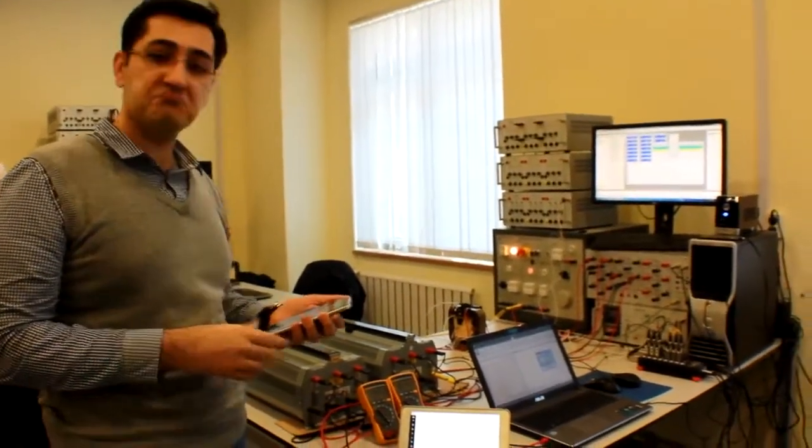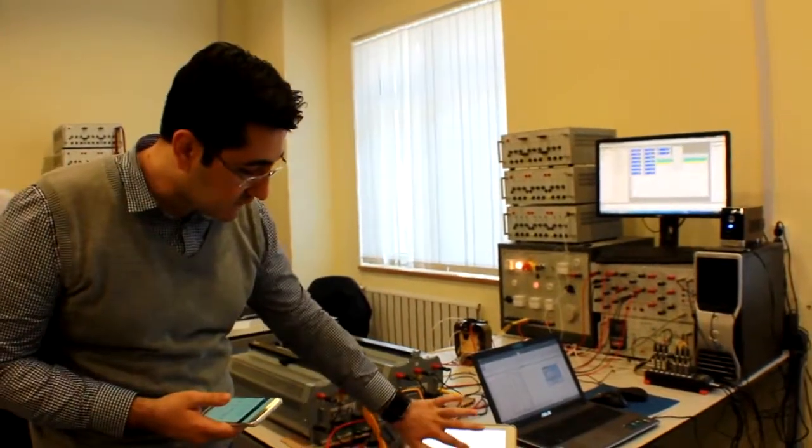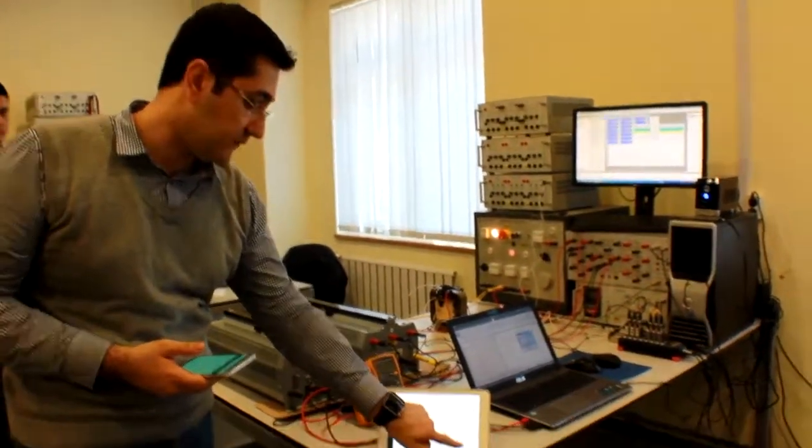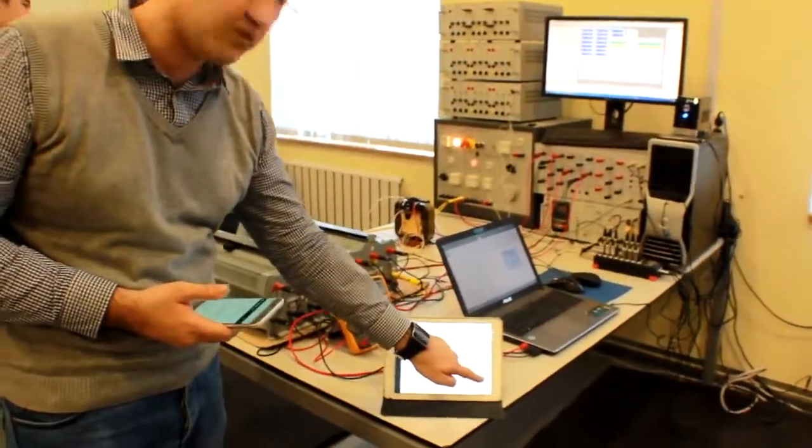By the way, we are still examining. We have to wait. Based on our simulation result, we have to wait for 4 hours until the transformer reaches end of life. This graph shows the end of life of the transformer. If you look here, we are starting at this point and it's going down. The trend is completely descending.